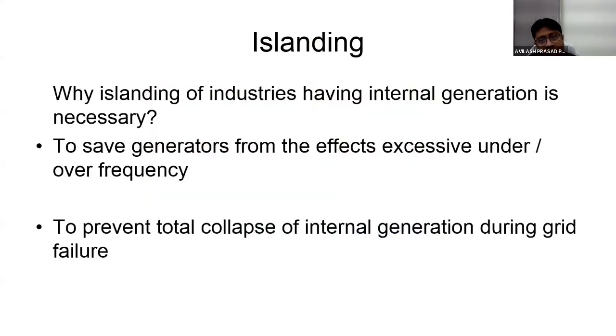Why islanding of industries having internal generation is necessary: to save the generators from excessive under or over frequency. Whether there is over frequency or under frequency, that may damage our loads or our connected motors. So it is necessary to prevent the total collapse of the internal generation during grid failure. If there is a grid failure, then our critical equipment should keep running. Otherwise, there is a collapse of the whole system.